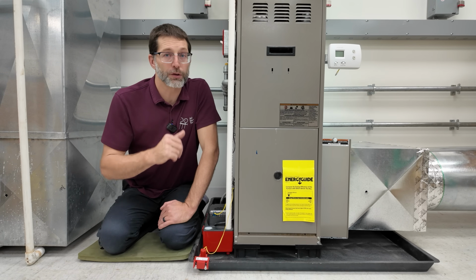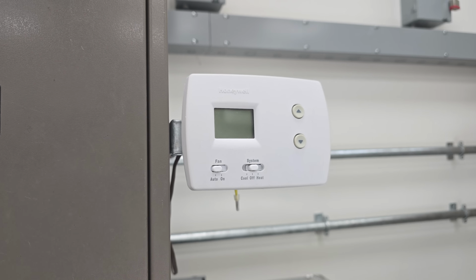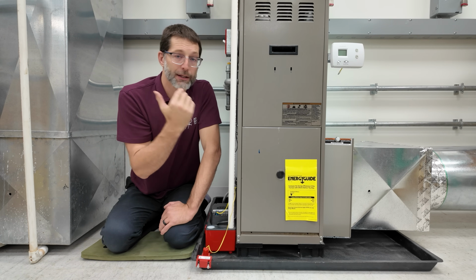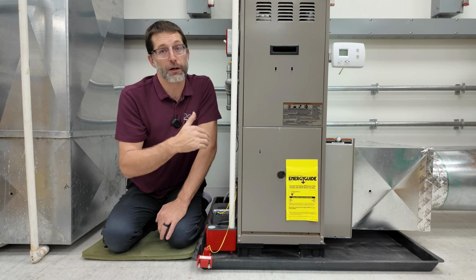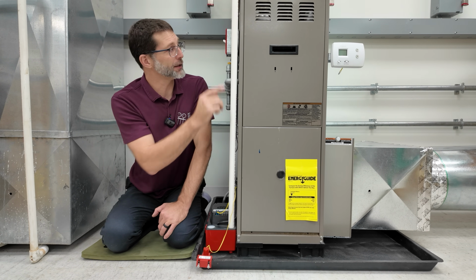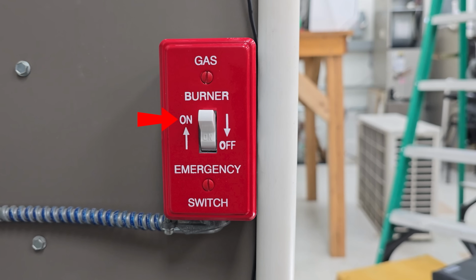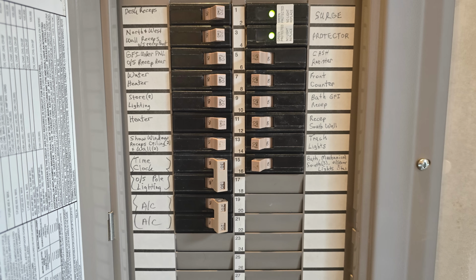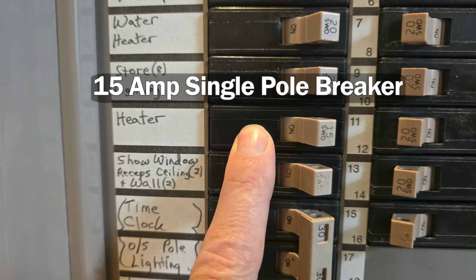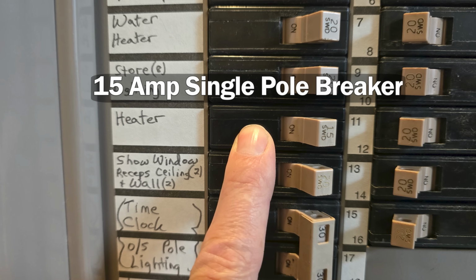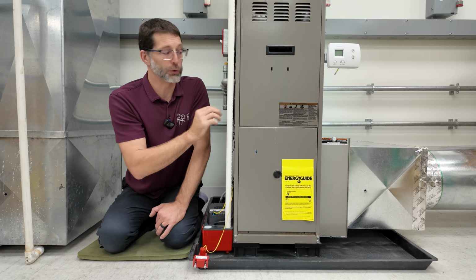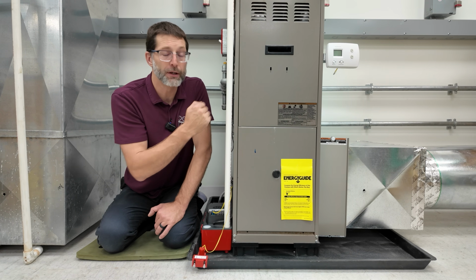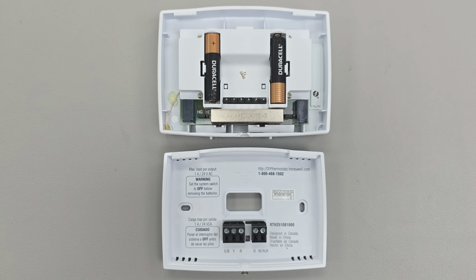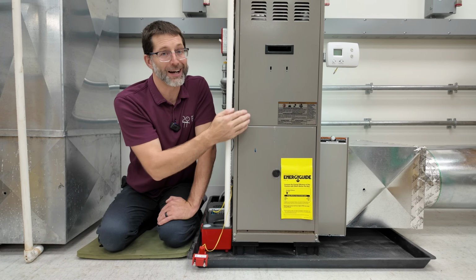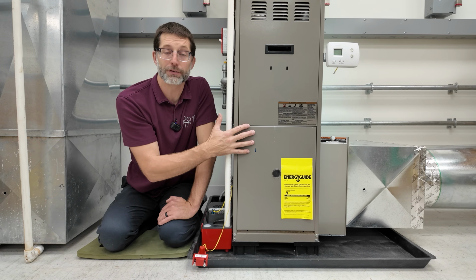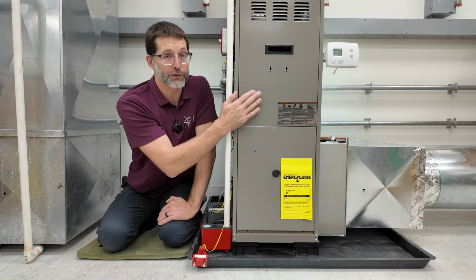When you arrive at the job site and you notice that you have a blank thermostat and the building owner says they can't get the heat to turn on, nothing's happening, the very first thing you want to do is check the emergency switch. Make sure that's in the on position. Make sure that the breaker itself for this, which is 120 volt, typically a 15 amp breaker for an indoor gas furnace, is on. Also keep in mind that some thermostats are battery powered and not hardlined into the furnace, but in this case, it is powered directly from the furnace, and that's why it's blank.